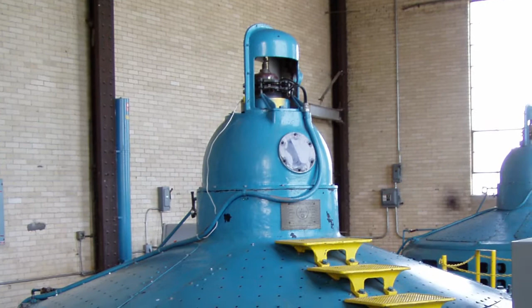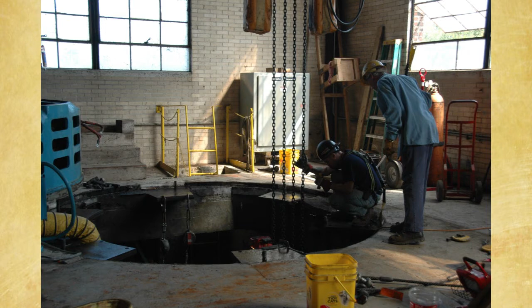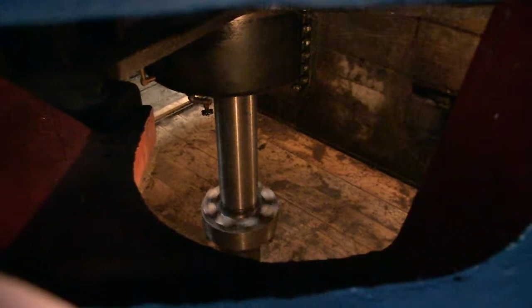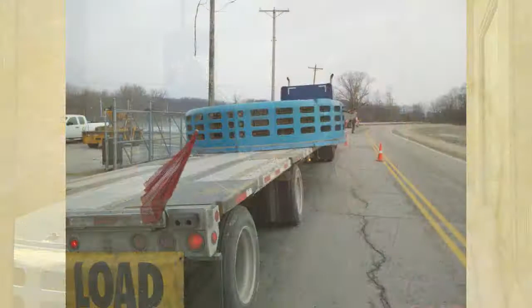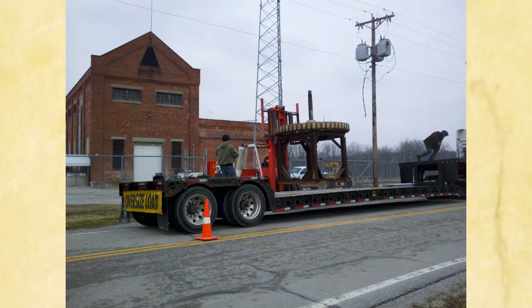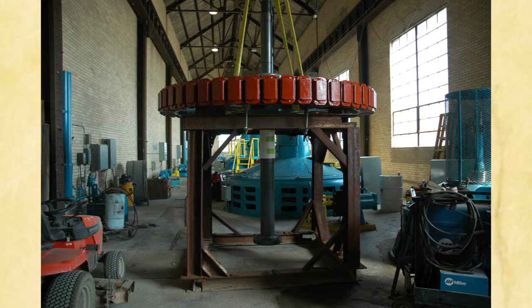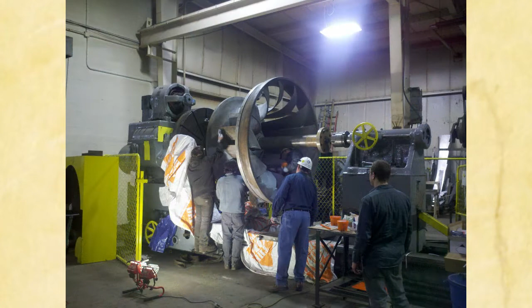Basically, we went through and had some major issues with the larger machines. Through the years, we've broken some large 8-inch diameter main shafts that are connected to the runner to the generator. So when we determined that those shafts were broken, we decided to go ahead and do major rebuilds on those units. The rebuilds consisted of sending the stator and the rotor out for rewinds, where they stripped all the old copper insulation, put new copper, new epoxy insulation on the machines, and then we sent out the runners to be balanced, cleaned, and new shafts built for them.